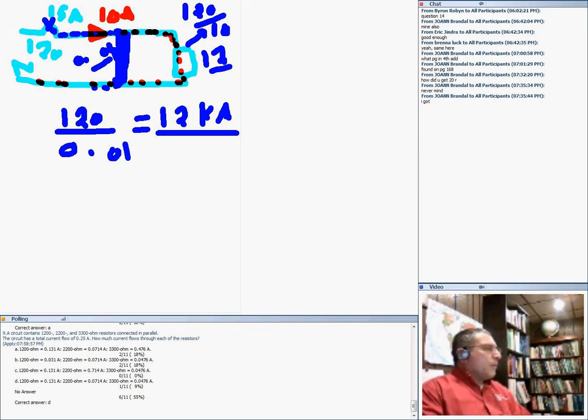Well, who cares? I want to tell you that you care all the time, guys. If you look at a circuit breaker, it has two values — roughly rated 10K. If the circuit breaker is 10K and the available short circuit exceeds that, you have burned your circuit breaker, Byron. That is very important — it explains why the short circuit current goes so high, because of the low impedance.